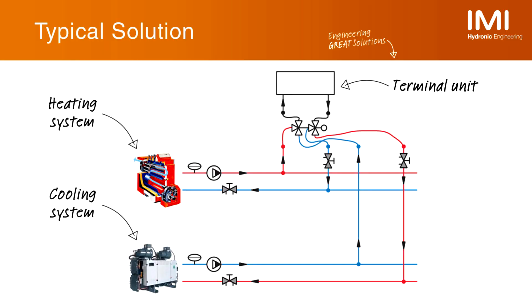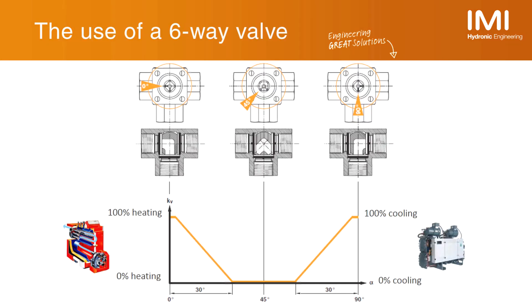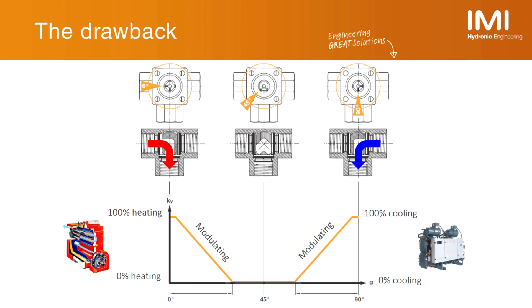Nowadays, a typical solution for changeover systems involves a six-way valve with its own actuator. The six-way valve is used both for switching the terminal unit from the heating to the cooling network and vice versa, as well as to modulate the flow. The drawback is that the six-way valve has to be able to control the flow in a stable and accurate way, allocating a part of its opening to heating and a part to cooling — typically 30 degrees of opening to each.